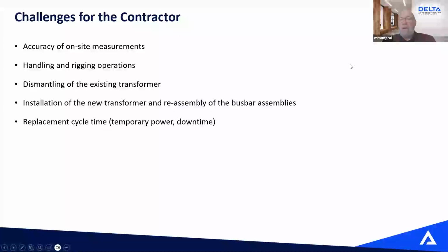The challenge for the contractor in the replacement of a medium voltage transformer is, first of all, the accuracy of the on-site measurement. The transformer will fit perfectly in place if the measurements were done properly. The handling and the rigging operation, again, bringing the transformer and its components into the electrical room is a challenge. That's got to be done properly. The dismantling of the existing transformer: if bringing a transformer into the room is a challenge, sometimes taking out an old transformer is also a challenge. It's got to be sometimes dismantled and cut in the electrical room. Then the proper installation of the new transformer and the reassembly of all the bus bars and everything. And they've got to figure out what's going to be the cycle time of this entire process, because again, I'm going to have to shut down the building. There's going to be a need to have temporary power. So that needs to be assessed and evaluated.